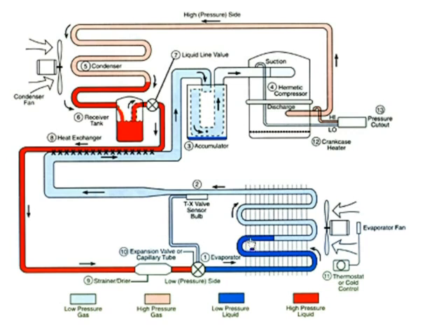And as it travels through there, we've got a fan that's blowing. Now this fan is blowing hot air on this cold coil, and the refrigerant is going to grab that heat. As it starts going through this coil, it's going to get heated up. Once it gets heated up to a certain point, that liquid's going to start changing to a vapor, and it's still going to try to grab as much heat as it can.